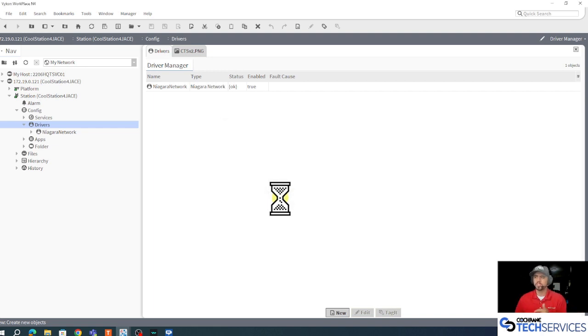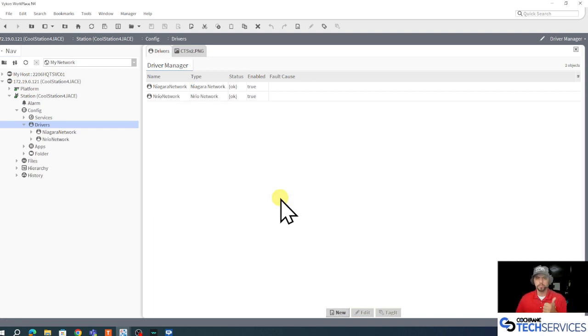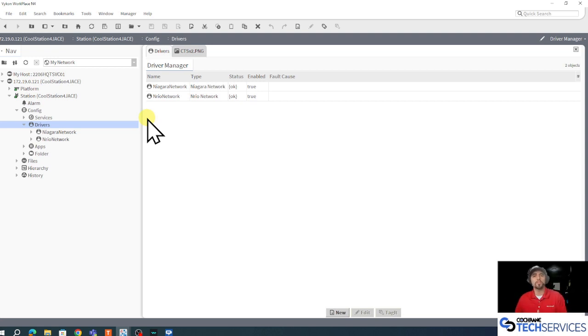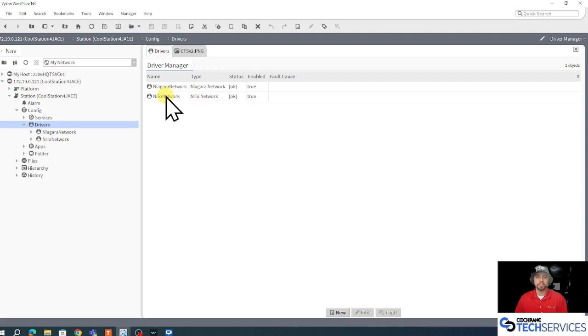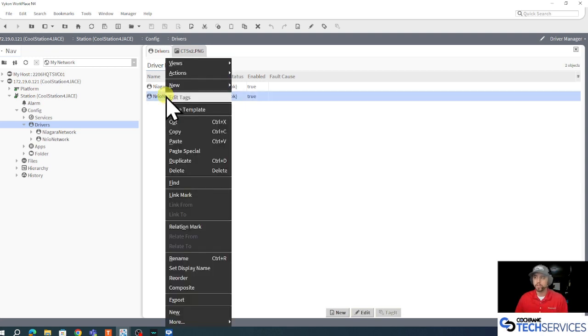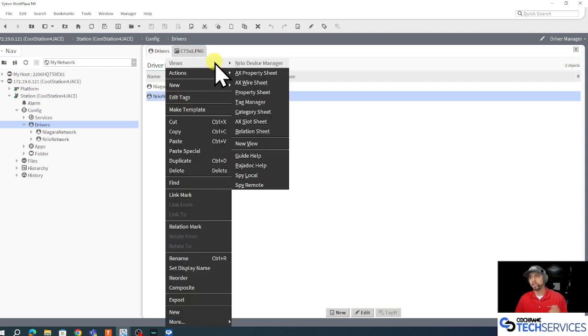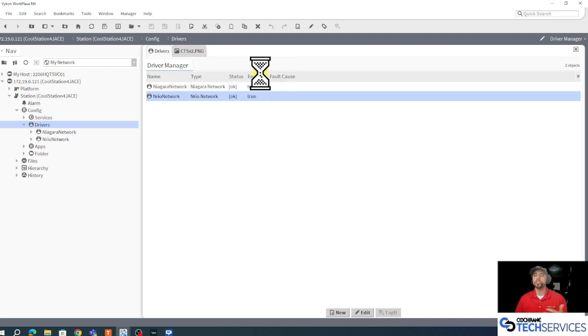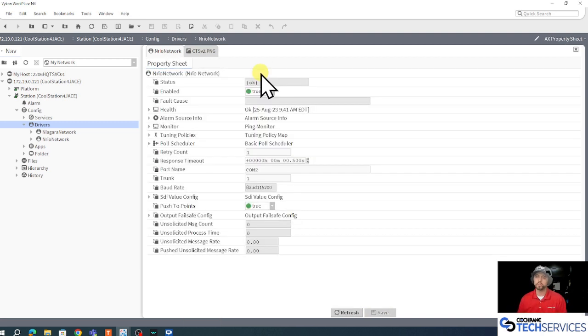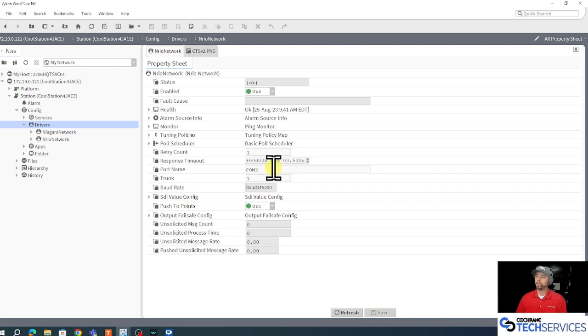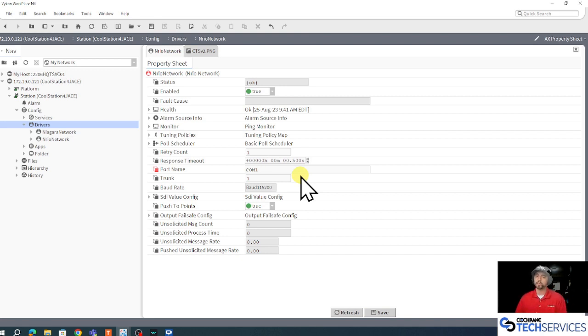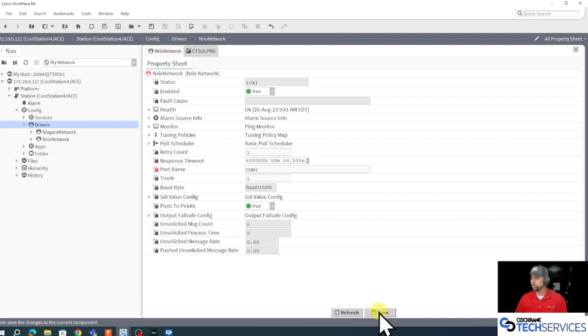So our NRIO network uses an RS-485 connection and our JACE 8000 has two of those native. So I'm going to right click my NRIO network and view its AX property sheet and choose which one of those COM ports to use. By default I'm using COM port number two, I'm going to change that to COM one, that's where I wired up our NRIO 16 device. Something's highlighted in red and I'll click save.